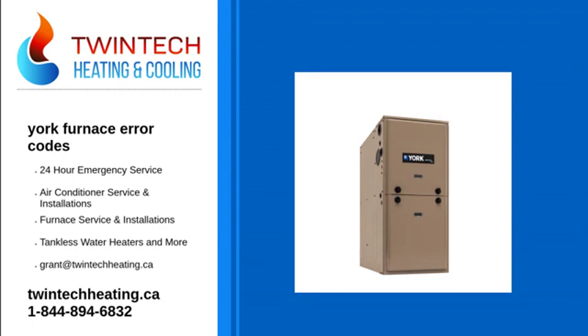Code: 6 red flashes. Result: this indicates that after the unit was operating, the pressure switch opened 4 times during the call for heat. If the main blower is in a delay on mode, it will complete it, and any subsequent delay off period, and the furnace will lock out for 1 hour and then restart.